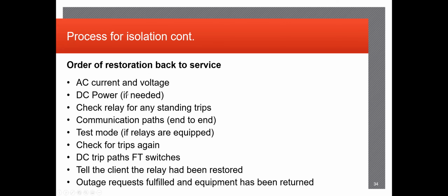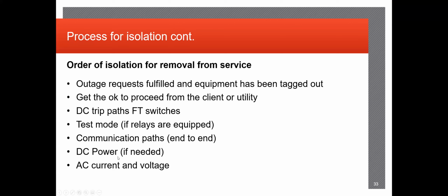So here we go. Oh, this is the restoration stuff. So yeah, in this case, the main thing is identifying your trip outputs, isolating those first, and then moving on to the rest of the equipment and finishing out with your currents and voltages. And then once your relay is properly isolated, you've powered it down completely, whether it be the AC or DC sources, you should be fairly confident, once you've done all your voltage checks and everything, that the relay is completely powered down. The electricians can get in there and get to work, whether it be replacing it or just taking it out completely.